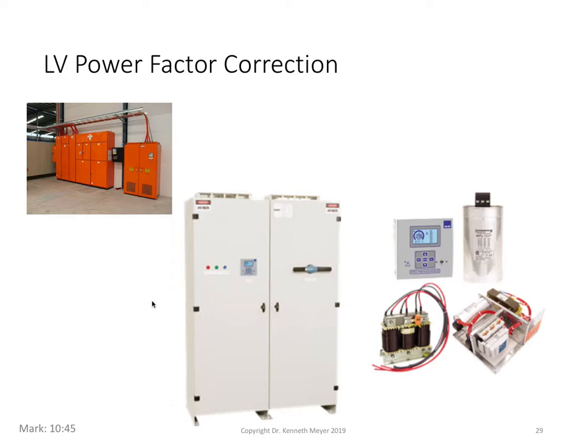Low voltage power factor correction. Here you can see a picture of a standard switchboard where my cursor is, and there's a power factor correction unit, and you can see a power factor meter. Basically, this is a power factor meter over here blown up. It simply measures the three voltages and the current on one of the phases. We assume that the loads are reasonably well balanced, so we only measure the current on one phase.